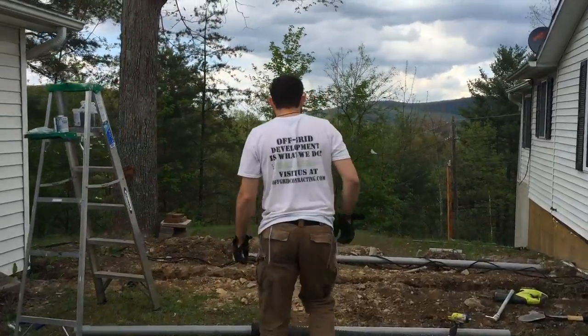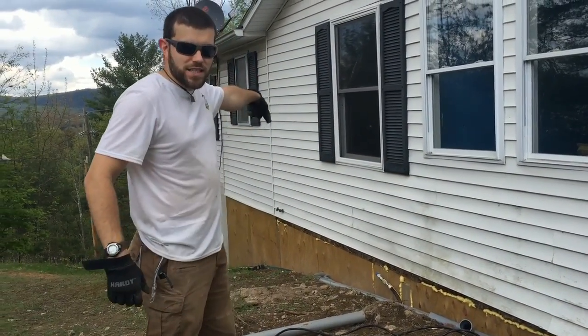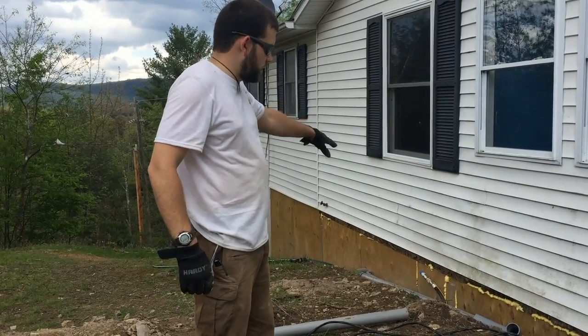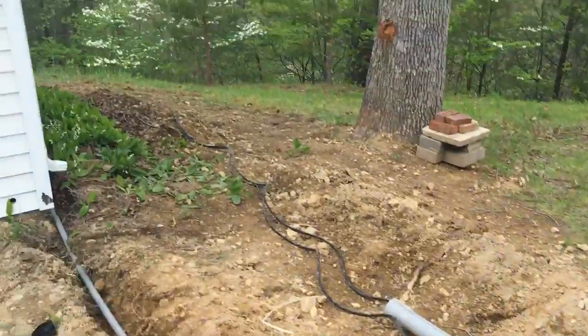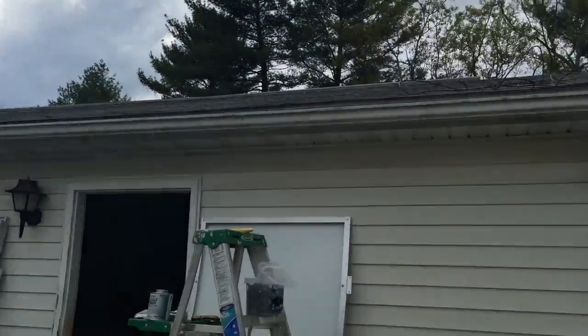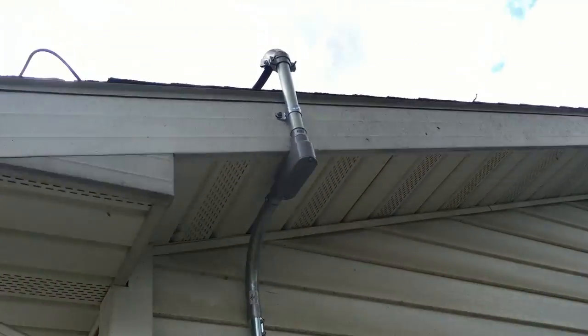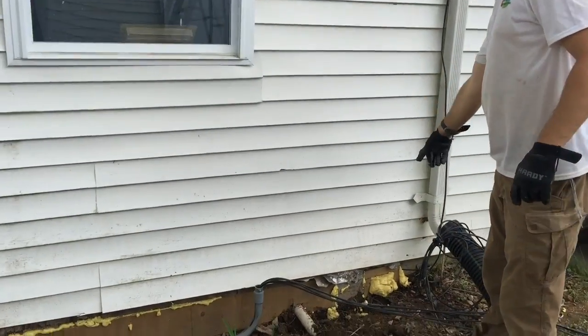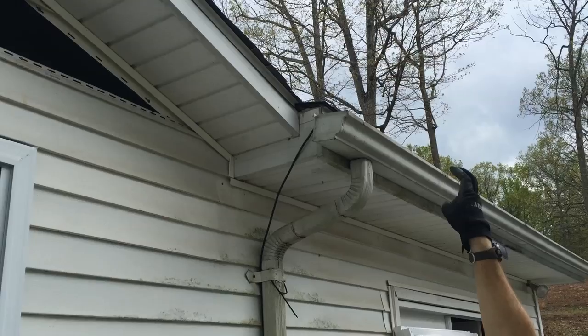If you want to step up here I'll show you what we're about to get into. We've got most of the bends done, we've got an actual junction box in there, and from there we divide out so we can stay with code. Right now you can see we've got our cables coming out for the wind power — that's going to go into the structure through the rafters and come out one at each side of the ridge cap. Our solar feed is coming out the conduit, then EMT, up to a weather head dropout. Over here we're coming out and going right up to the corner, neatly tucked behind the gutter, putting the weather head up away from the washout.